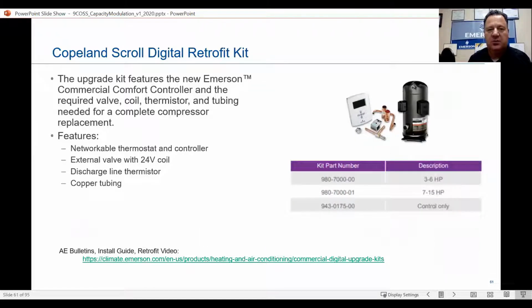There's also a Copeland Scroll digital retrofit kit. The upgrade kit features the new Emerson commercial comfort controller and the required valve, coil, thermistor, and tubing needed for a complete compressor replacement. It features a networkable thermostat and controller, an external valve with a 24-volt coil, and the discharge line thermistor, which is huge, and then some copper tubing. You've got your kit part numbers here and the description on where the horsepower falls, all right? See if we can get this to play for you.